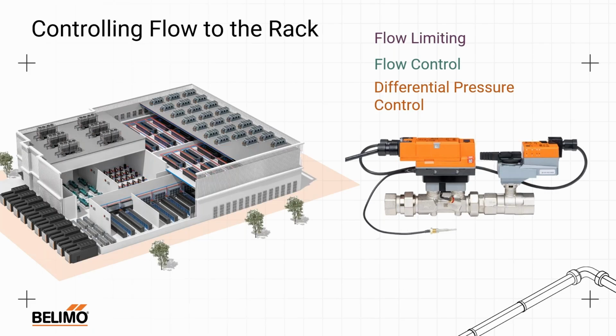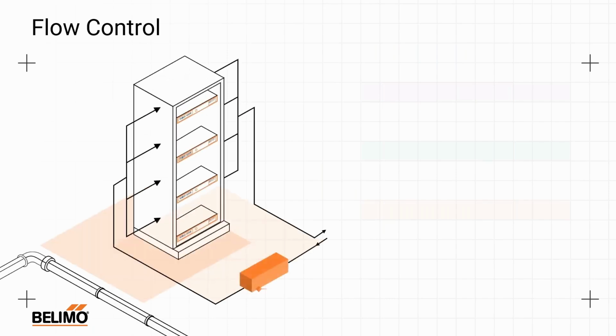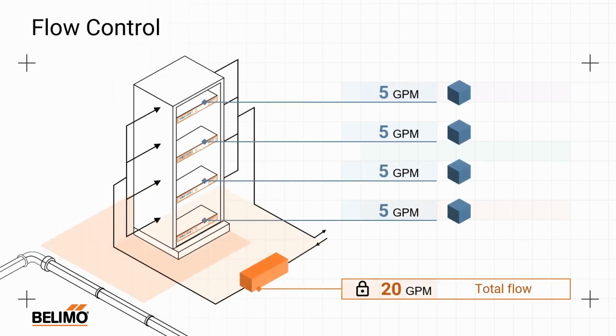You're probably sitting there thinking, if I can control directly to 10 gallons a minute, why would I switch to some other form of control? What gain am I getting? Well, let's break down to the rack level of how these controls work. So let's go ahead and build ourselves a liquid-cooled rack. And maybe for simplicity's sake, we'll say we have 4 servers in there. Each requires 5 gallons a minute for a total flow control of 20 gallons a minute.